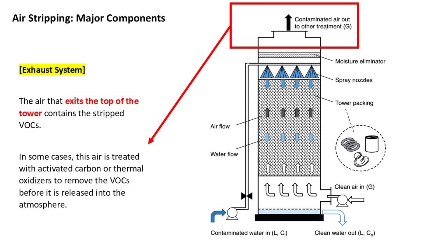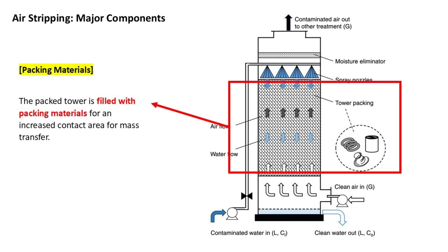The exhaust system handles air that exits the top of the tower, which contains the stripped VOCs. In some cases, this air is treated with activated carbon or thermal oxidizers to remove the VOCs before it is released into the atmosphere. In a typical air stripping process, groundwater containing VOCs is counter-currently contacted with air in a packed tower filled with packing materials for increased contact area and mass transfer. Contaminated water enters at the top, flows down by gravity, and air is fed upward from the blower at the bottom. The VOCs are transferred to the gas phase during intimate gas-liquid contact, and the equilibrium distribution between gas and water phases is described by Henry's Law. The VOC-laden exhaust air must then be treated by passing it through an activated carbon column.